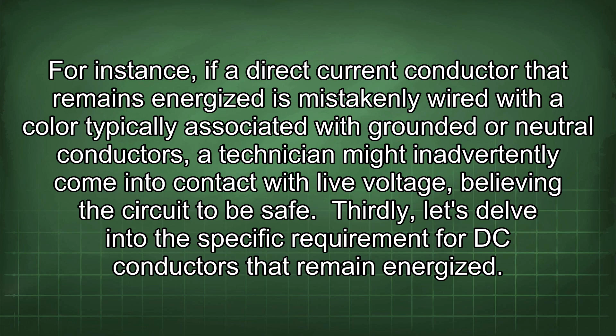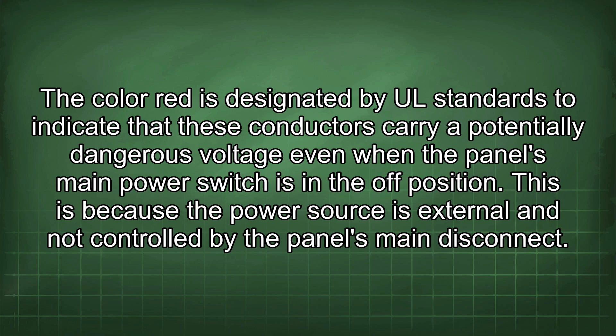Thirdly, let's delve into the specific requirement for DC conductors that remain energized. The color red is designated by UL standards to indicate that these conductors carry a potentially dangerous voltage even when the panel's main power switch is in the off position. This is because the power source is external and not controlled by the panel's main disconnect.